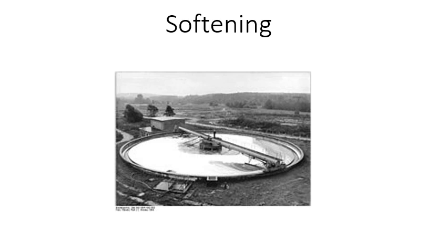Limitations of softening: free chlorine is not as powerful in the hypochlorite ion form, which occurs at the higher pH levels. The cost versus benefits: for every 1 ton of lime used, 2 to 3 tons of waste is produced. You have to dispose of that waste. Trihalomethanes form at the higher pHs if using free chlorine. If water has color in it, the high pH can set the color in place, making it harder to remove later. So for waters with high color, it's recommended to use the coagulation flocculation process to remove the color before softening.